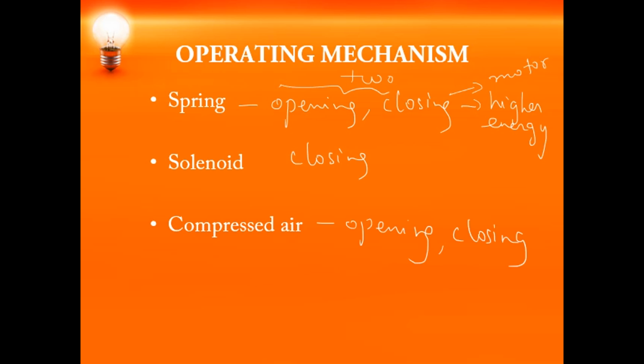In the case of vacuum circuit breaker, we have a solenoid or a spring mechanism which is fixed to the lower end of the metallic bellows, or it will be placed inside the chamber during closing or opening of the contacts, and the closing mechanism will be trip free. When we compare these three, that is spring, solenoid and compressed air, springs are actually very good for opening, and for closing it is not preferable usually.